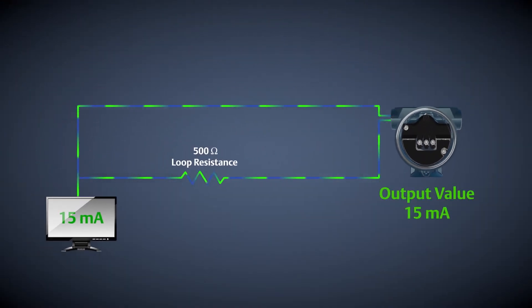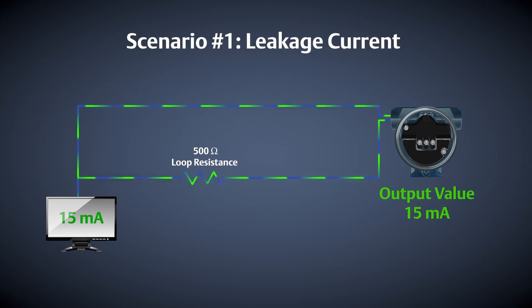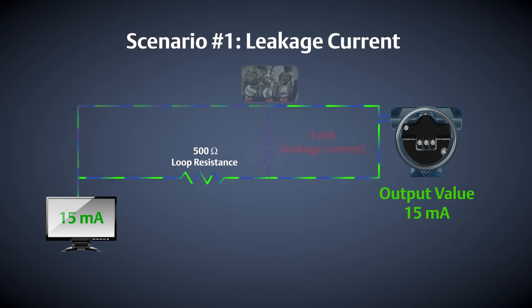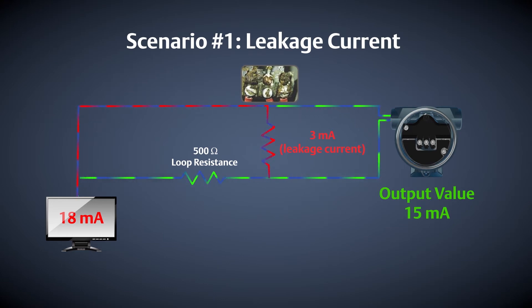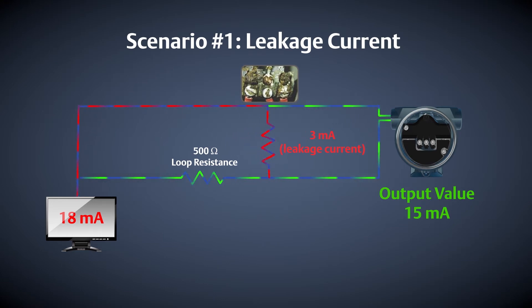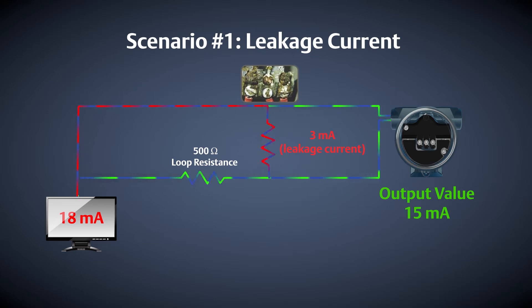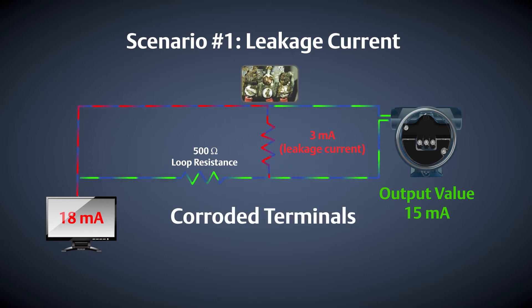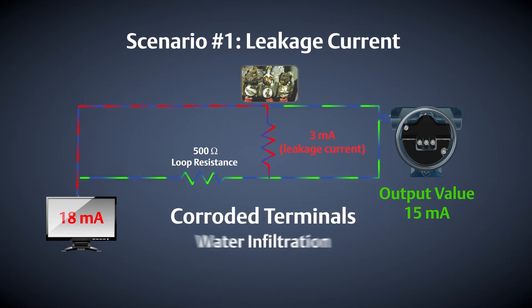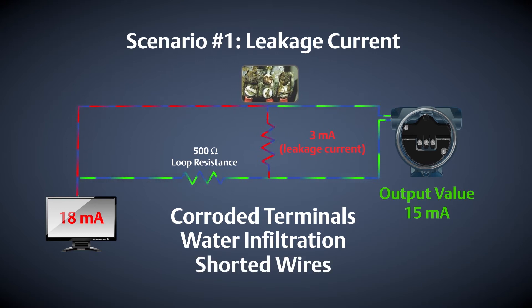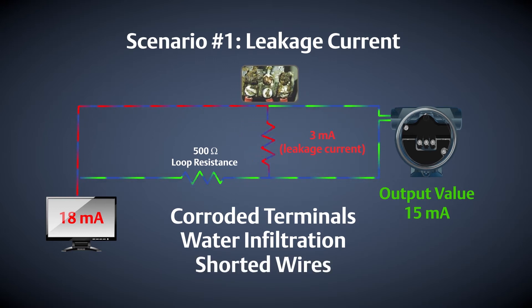Let's picture two scenarios which can lead to on-scale failures. The first scenario is a circuit that has leakage current, which is an electrical issue where an additional current path is created in the wiring. Leakage current can be caused by a number of human or environmental factors, including corroded terminals, water in housings or conduits, shorted wires, and others.